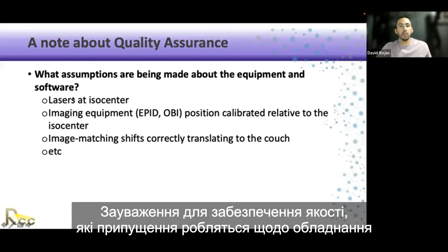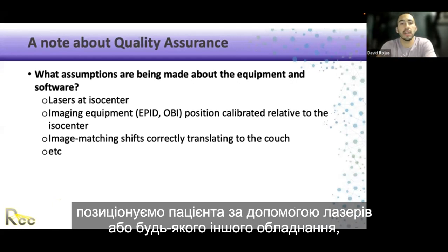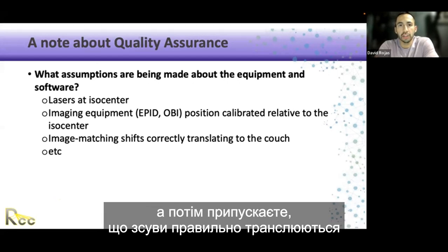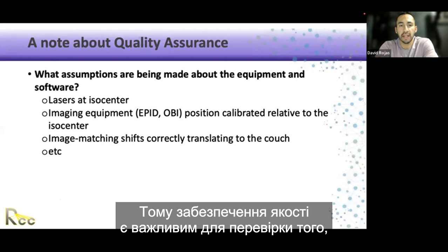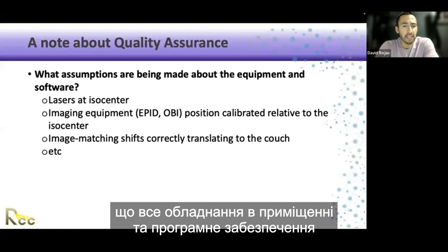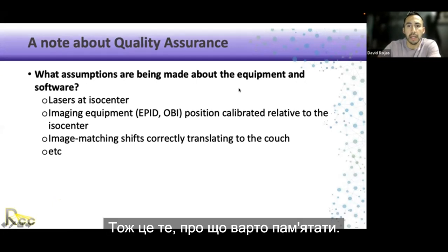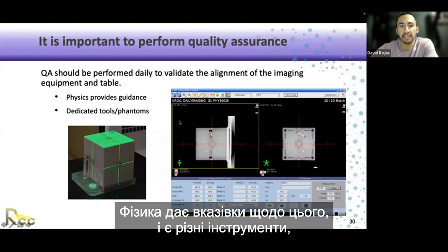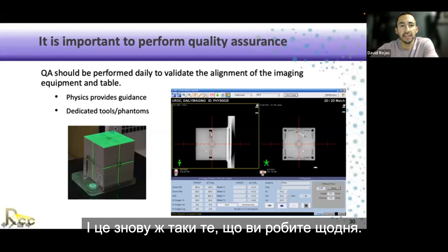A note for quality assurance: you're positioning the patient using lasers, stepping out, taking an image to verify position, applying shifts in software, and assuming those shifts are translating correctly to the treatment table. QA is important to verify that all equipment and image matching software is operating appropriately to a specific tolerance. QA should be performed daily to validate the alignment of imaging equipment and table. Physics provides guidance with different tools, phantoms, and software to verify everything is working accordingly.